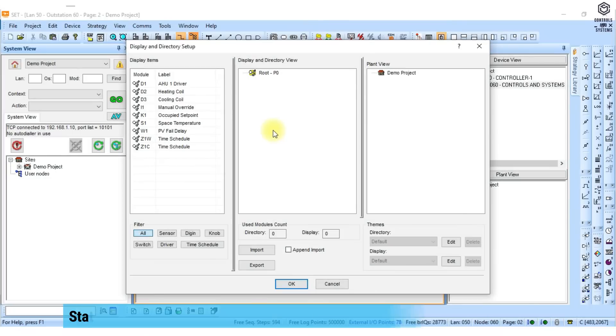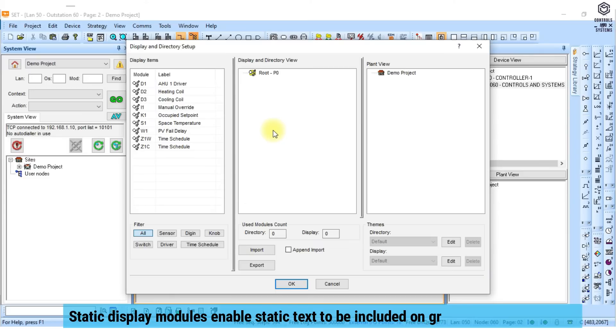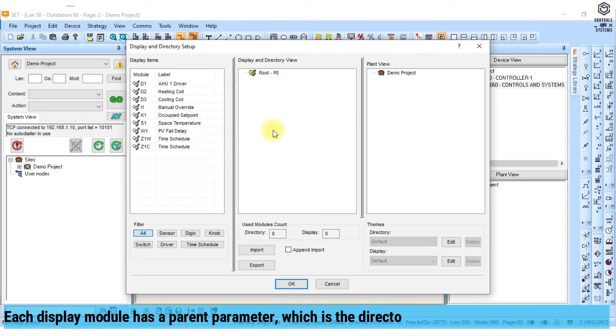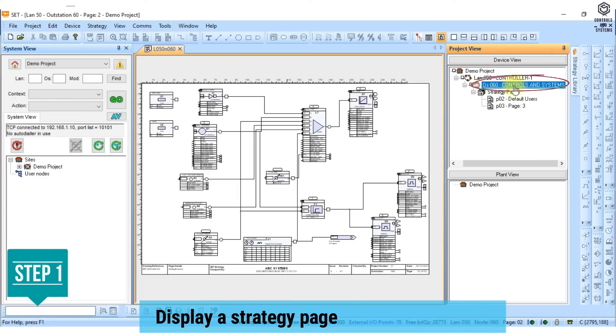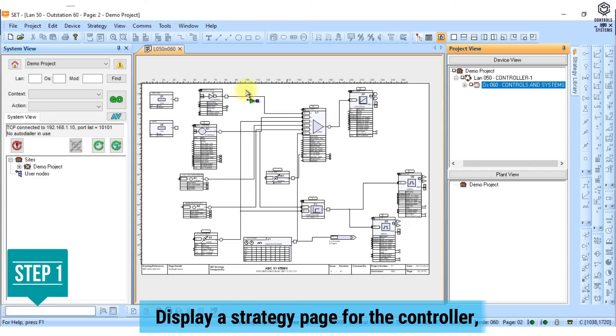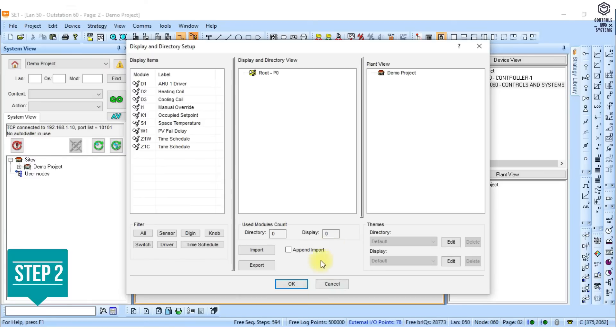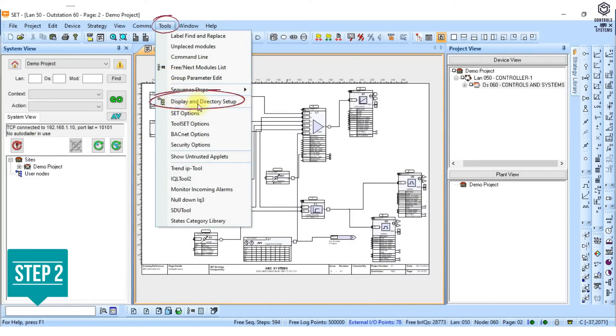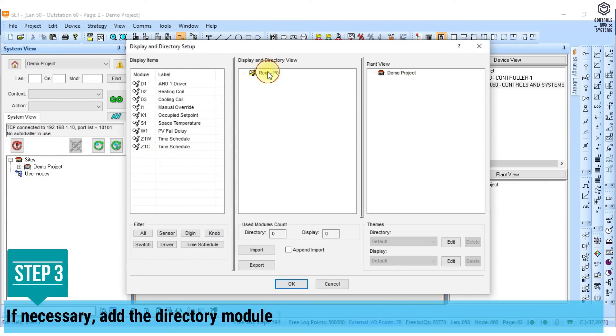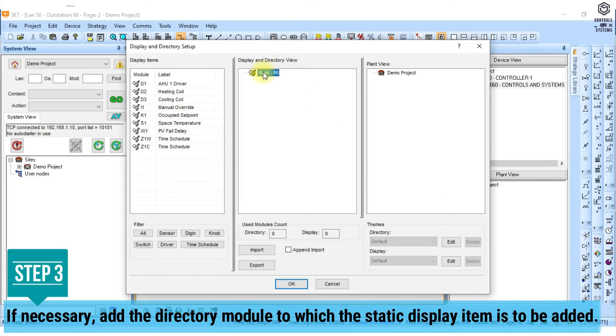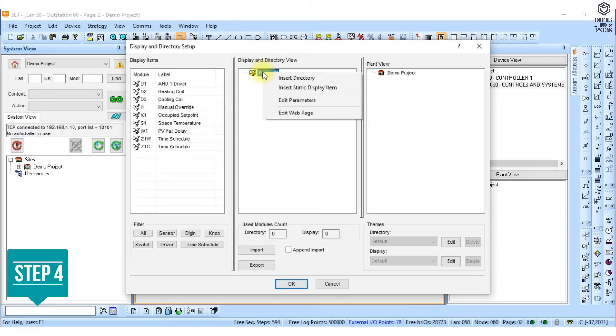Add a static display module. Static display modules enable static text to be included on graphical display pages. If required, the static text can be set to be a link to any specified URL. Each display module has a parent parameter, which is the directory module to which it is attached. 1. Display a strategy page for the controller. 2. Click on this symbol, or on the tools menu click display and directory setup. The display and directory setup dialog box is displayed. 3. If necessary, add the directory module to which the static display item is to be added. 4. Right click the directory module that is to contain the static display module and click insert static display item.